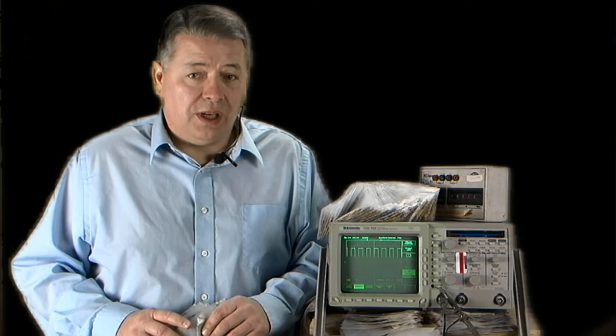What once took several hours to set up and adjust can be done now in minutes. Finally, while it does a great job on most systems, there are, however, some systems that will elude the auto-tuner because of the complexity of the mechanics or the compliance of the components. For these, manual tuning must take place.